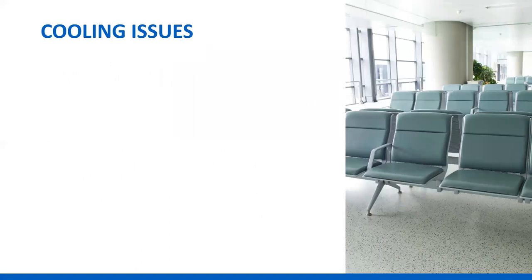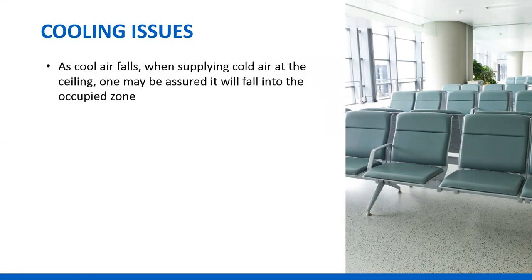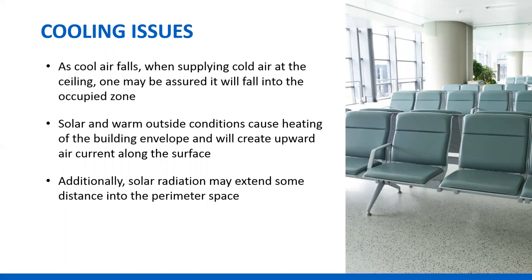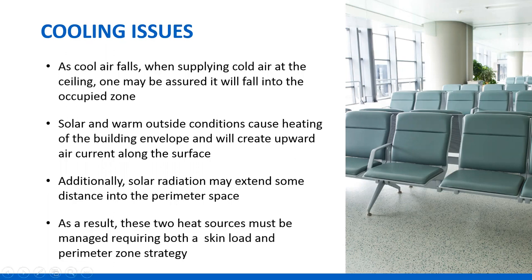Cooling is an interesting issue. You heat at the glass, but for cooling you've got to cool as far in as the sunlight will penetrate — in fall and spring when the sun is lower and it's still warm out, that can be quite a distance into the perimeter zone. As cold air falls, it's going to make it to the floor. We don't have to worry about cold air short circuiting. Because we need to deal with solar going further in, we may get upward air currents along the window surface and heat generated by furniture in the interior zone.